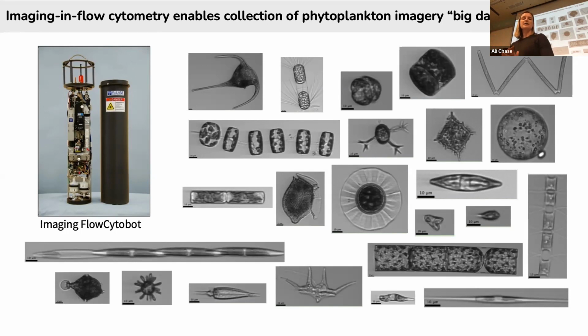It's set up in the lab and it's attached to a flowing seawater system. It's designed to draw a sample of about 5 milliliters a few times an hour, and then pass the water through the fluidics and capture a picture of every plankton found in the sample. In this way, it can record thousands of images in an hour or millions over the course of a multi-week expedition.